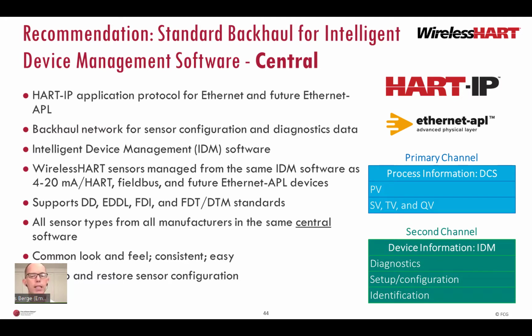WirelessHART sensors can be managed from the same IDM software used for the plant's existing HART and fieldbus, as well as future Ethernet APL instrumentation. Even IDM software based on FDT DTM can be used to manage WirelessHART sensors by installing the DTMs for the gateway and sensors. Other technologies cannot achieve the same result because they either don't support EDDL or FDI, or they don't have a standard backhaul protocol like WirelessHART, preserving the message format and data types for the configuration and diagnostics information.